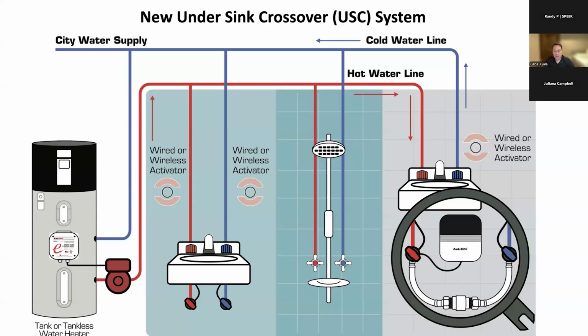And then we have another product. Let's say you have an existing house that never had a return line put in, so there's no recirculation line. Maybe the house is a few years old, and the homeowner has always suffered with long hot water wait times, but they want to have a circulation system. Maybe they don't want to spend the money to have a plumber come in and repipe and put a return line in. We have an option that's an easy retrofit that can be incorporated into any building or home.